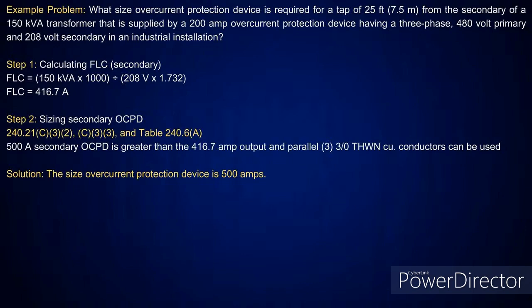Okay. So in here, we're going to size the overcurrent device required for a tap of 25 foot from the secondary of a 150 kVA transformer. Now, remember, we put this in there on purpose, telling you a tap on the secondary side, because a lot of people used to say just tap the secondary side of that transformer, when in reality, there are conductors on the secondary side of a transformer. Therefore, you're not taking at a third. A tap is where you're coming down from a feeder and tapping off of that feeder.